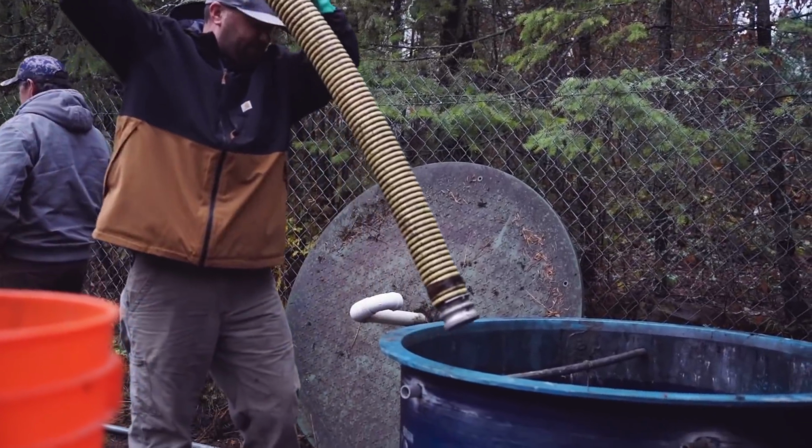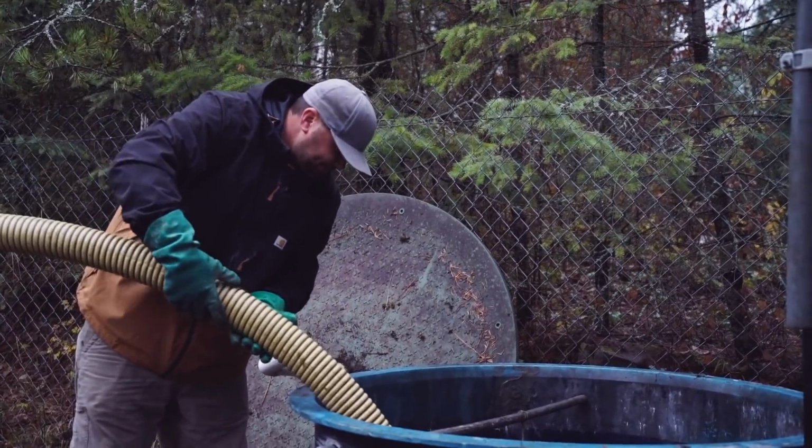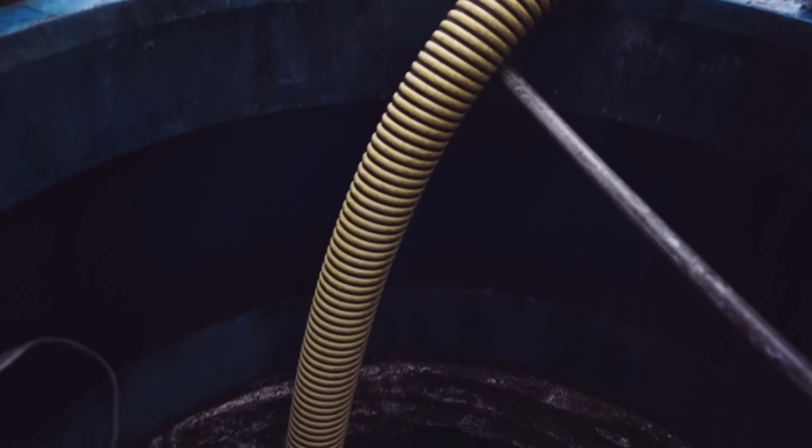The tank was overflowing. We had an emergency, had to call Ace. They are a pumper company, and they pumped down the system so we could get in it and change the pumps. When the pumps were mounted in there, whoever did it, they put everything at the bottom of the lift station, which made it extremely difficult to try to change because everything had 8 feet of poop on top of it.